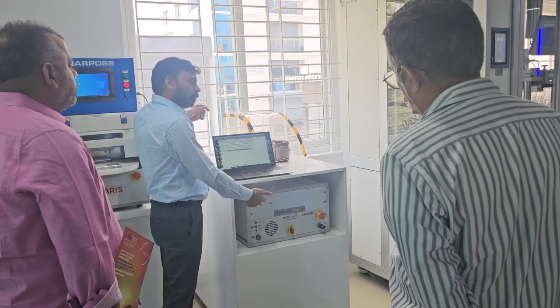Whatever electrical testing of the stator is required will be done by this equipment, even for voltage more than 400. We give a high voltage through this equipment, and it does high voltage testing, impedance test, resistance test, and many other electrical parameters. So all EV manufacturers, as well as motor manufacturers, must be taking it up for their assembly, because many companies in India are already using this equipment.